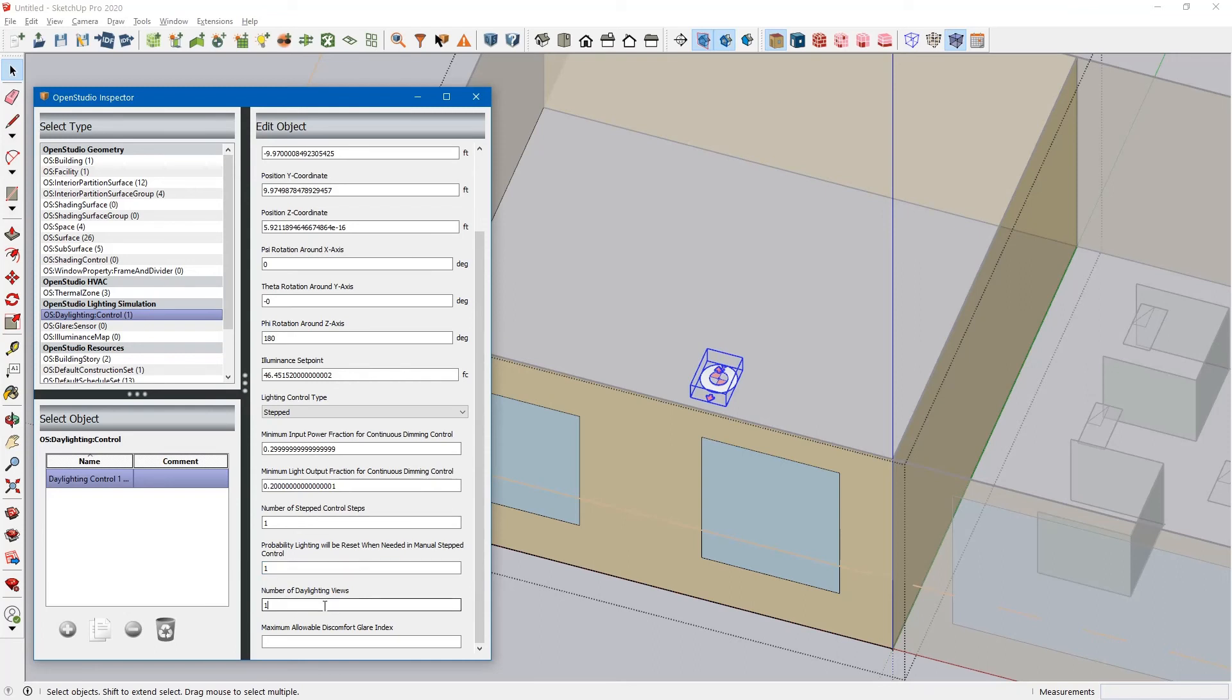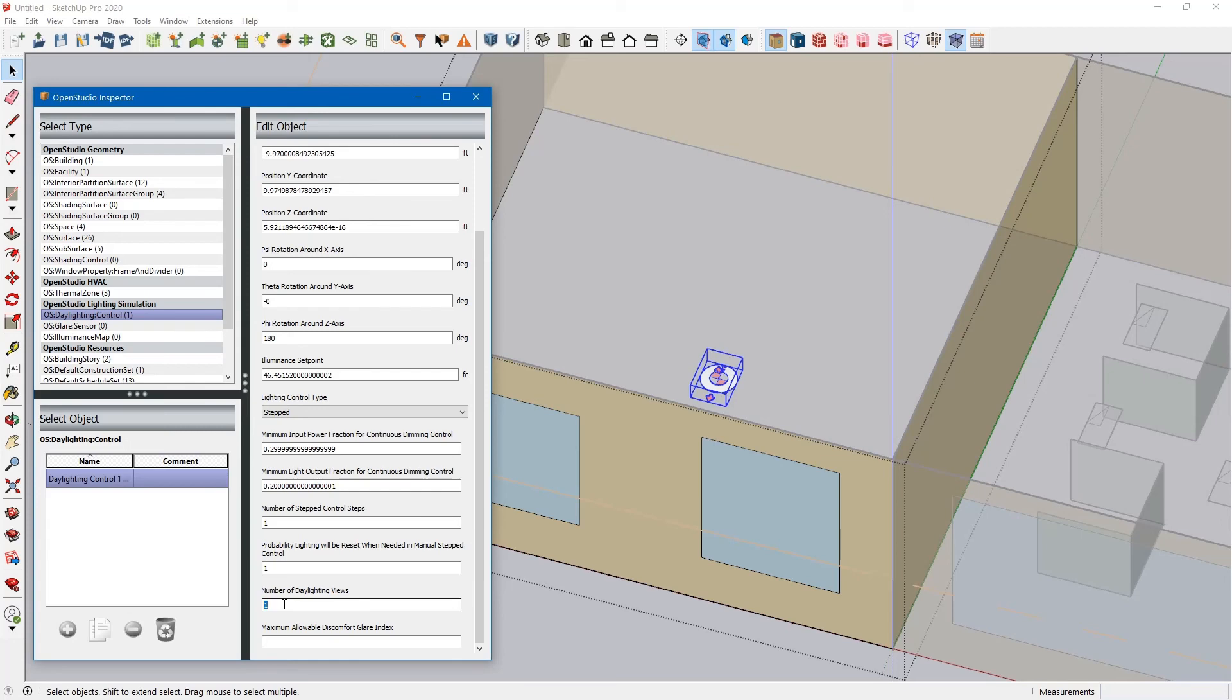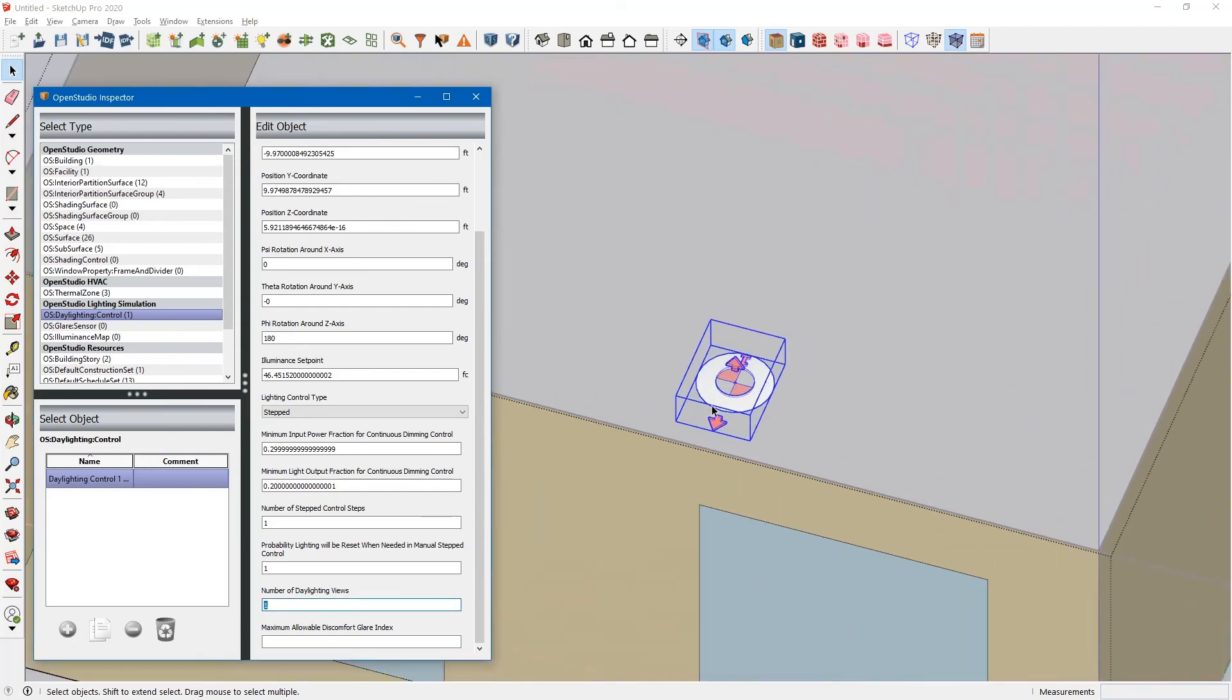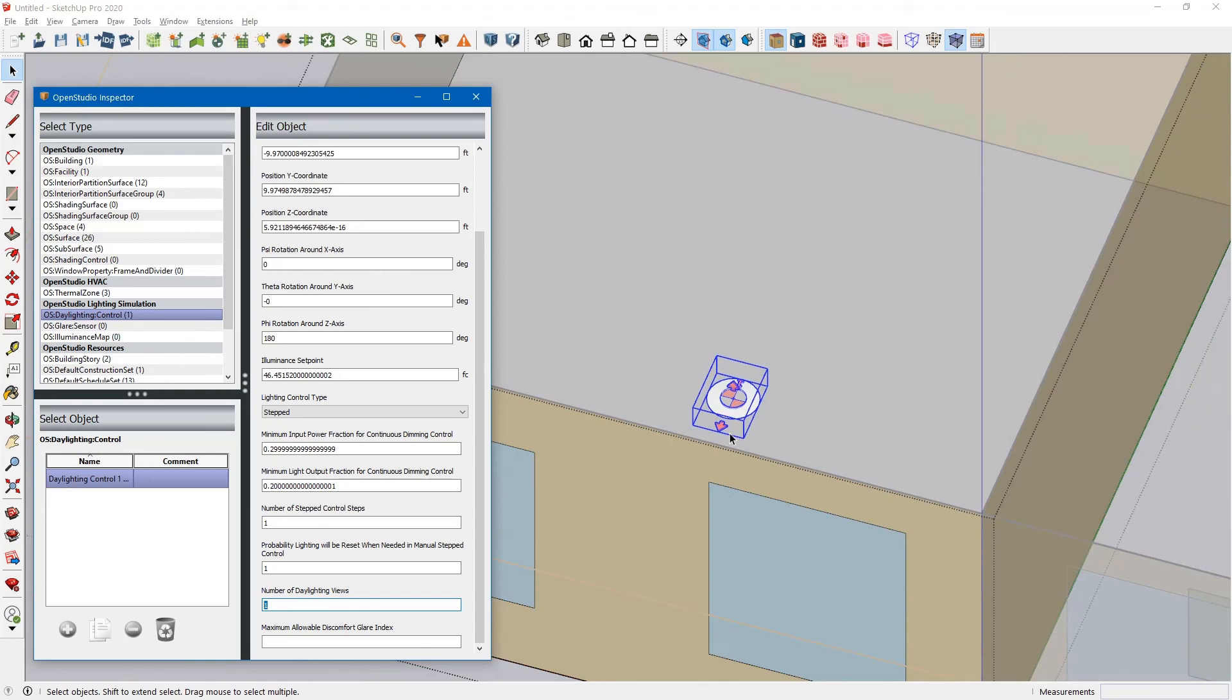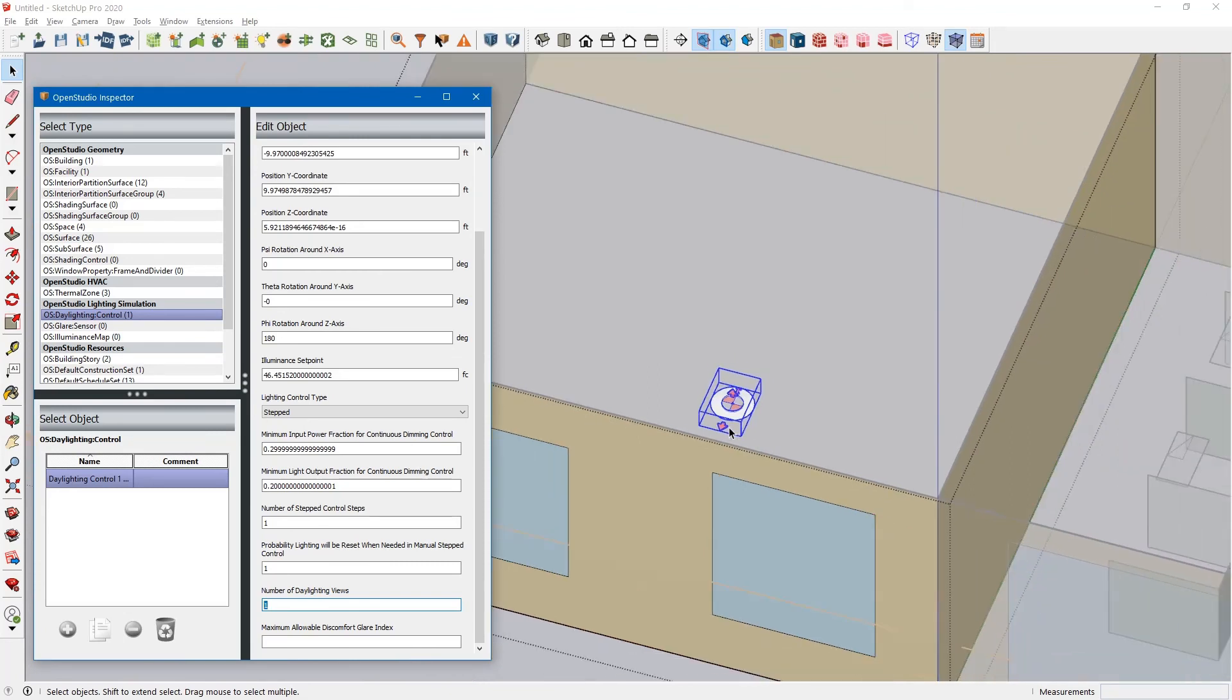The number of daylighting views for this. I don't believe this factors into Energy Plus, but if you are going to be running Radiance, the Radiance measure in OpenStudio, then this number of daylighting views comes into effect. And I believe it multiplies the number of these arrows here. So it will equally space the arrows out throughout the room to get a better understanding of how well the entire room is daylit.